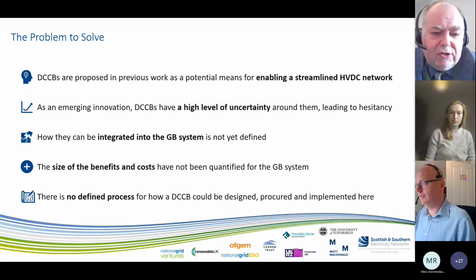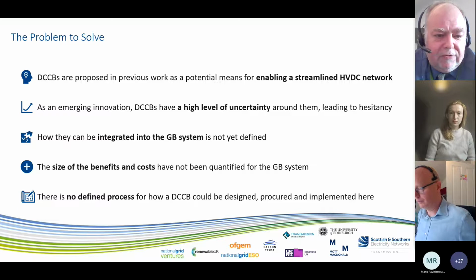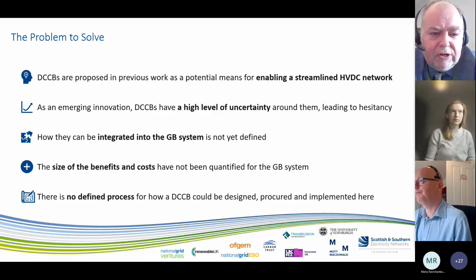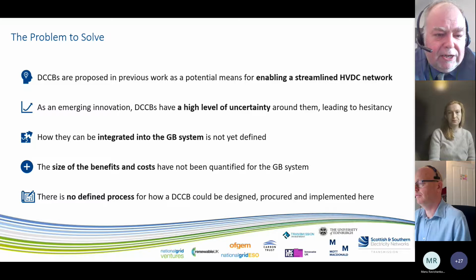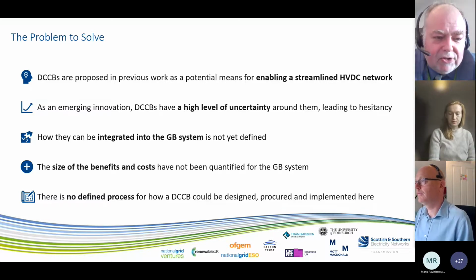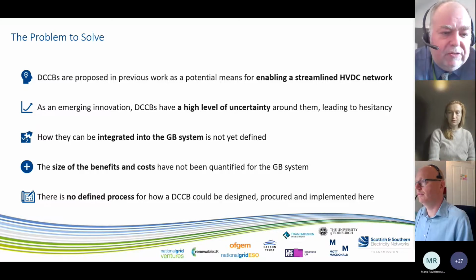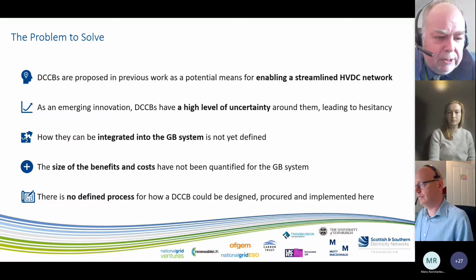Now we mentioned the uncertainty. The key uncertainty is the difference between China, where live testing is very much part of the verification of circuit breakers. Actual faults, AC and DC, are applied to these networks to verify the simulation analysis and to hone the specification of those DC circuit breakers. There's been an evolution in specification in China based on their deployment of projects over subsequent developments of technology. They've modified the overloads, they've modified the durations that DC circuit breakers are expected to operate over.